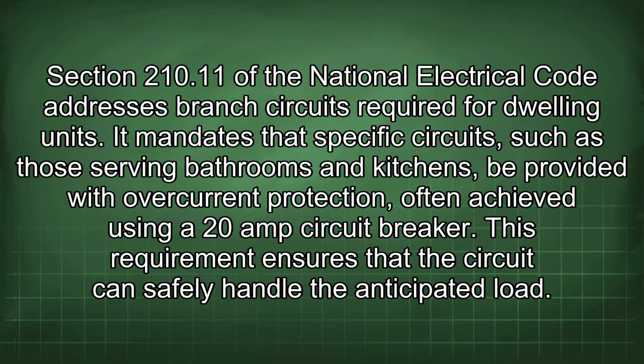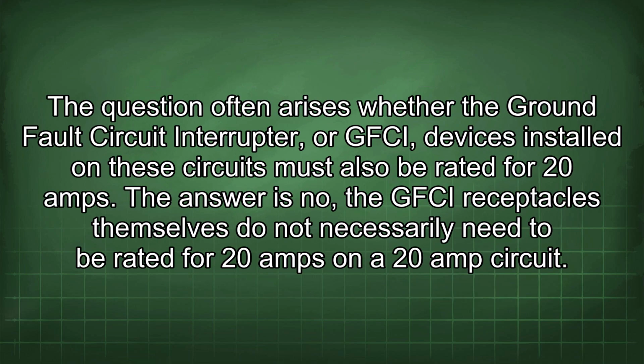Section 210.11 of the National Electrical Code addresses branch circuits required for dwelling units. It mandates that specific circuits, such as those serving bathrooms and kitchens, be provided with overcurrent protection, often achieved using a 20-amp circuit breaker. This requirement ensures that the circuit can safely handle the anticipated load. The question often arises whether the ground fault circuit interrupter, or GFCI, devices installed on these circuits must also be rated for 20 amps. The answer is no.